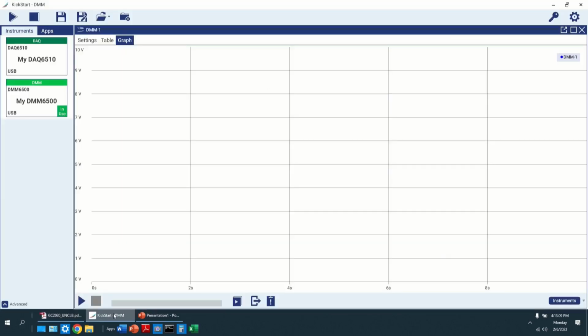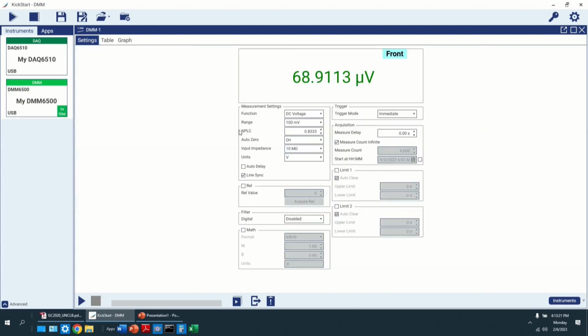I'm using a Keithley meter to record the data, and I'm using the Keithley Kickstart DMM app. I have 2 meters, a DAQ 6510 and a DMM 6500. The settings are that it is a DC voltage 100 millivolts full scale, an NPLC factor of 0.8333 to lock sampling to the line voltage. That will result in 50 samples per second. Auto zero is on. Input impedance is 10 megohms. Units is volts. And I sync to the power line.